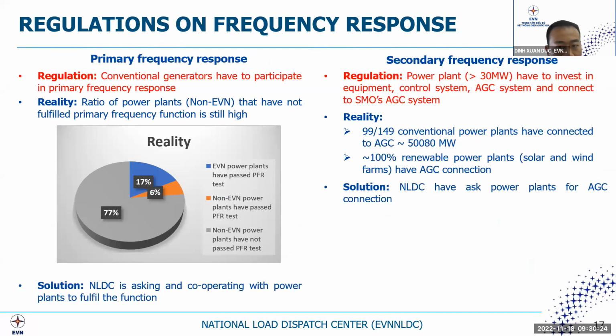Up to now, from NLDC, we have put a lot of requirements into the grid code, requiring not only conventional power plants to participate in primary and secondary frequency control, but also reclaiming contribution from renewable energy for primary frequency control, especially solar. In the case of higher frequency, they have to reduce output, and we have put the same regulation in place for wind.